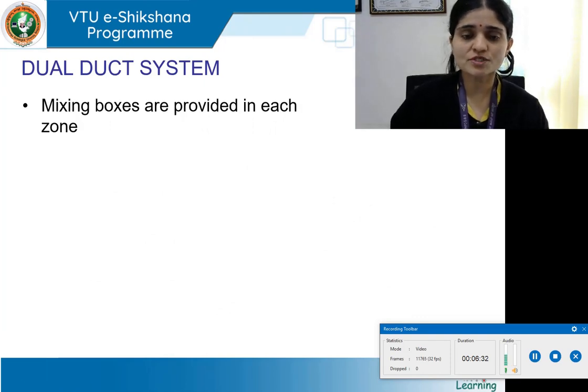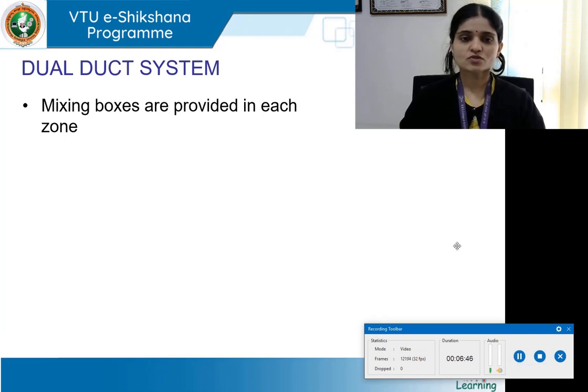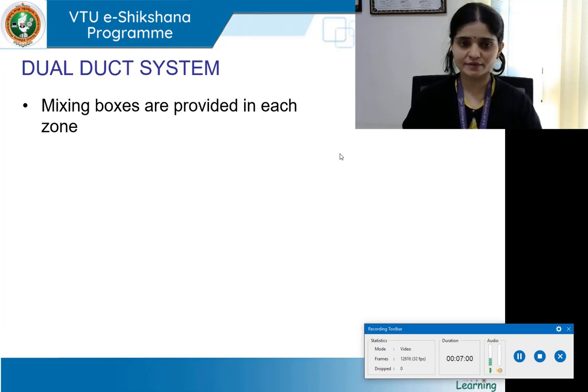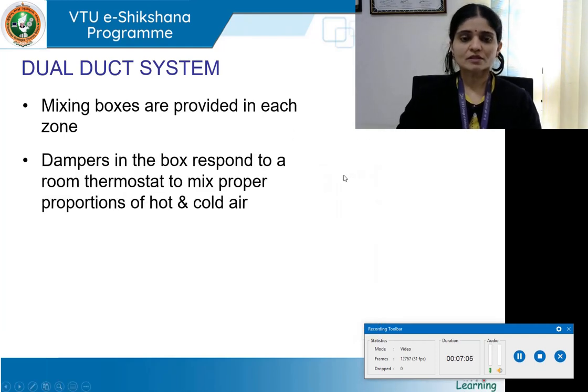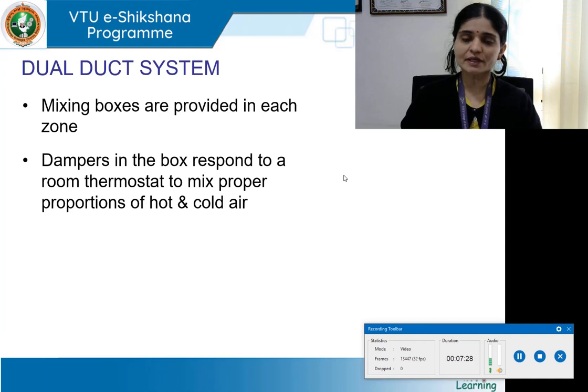The mixing boxes are strategically placed under each zone. Dampers — controlled openings or small gates — in each mixing box respond to a room thermostat to mix the proper proportions of hot and cold air. The damper controls the quantity of air and determines how much hot and cold air to mix to achieve the required thermostat parameters for that zone.